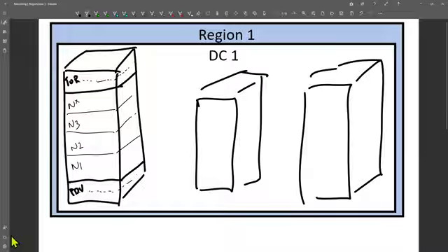There's 2 of them so that every node that is in this rack is redundantly connected to at least 2 different sets of power that have 2 different sets of power backup and generators and all that stuff. So we have highly redundant power to this scale unit. At the top, we have 2 TORs that also have network connections.